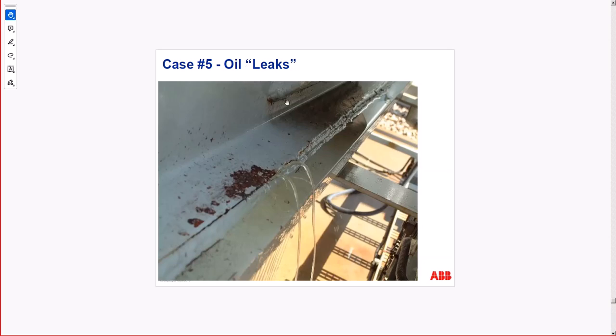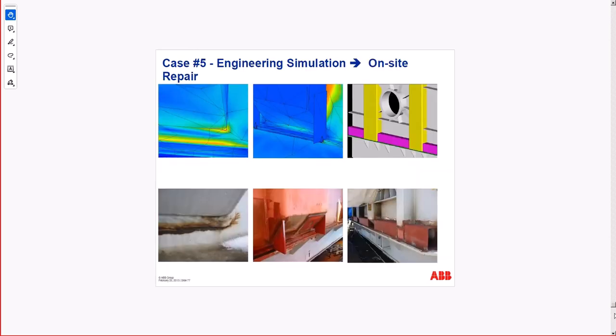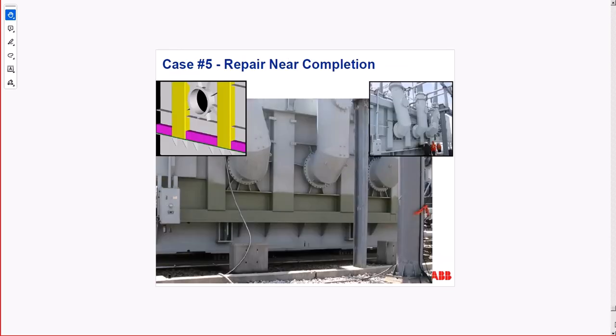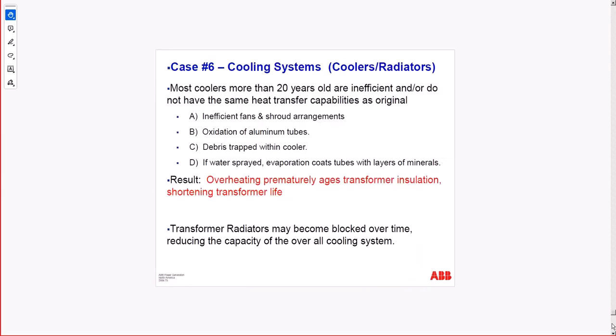So oil leaks, you can see here coming out of the tank. Keep in mind, whenever the oil comes out, the air goes in the same spot. Not only do you get lower oil and cooling, but you get moisture getting inside at the same time. Simulations, on-site repairs. There are different software to simulate the forces, the distribution of the temperature and cooling of the transformer inside. Here is the same transformer with the repair done on site.